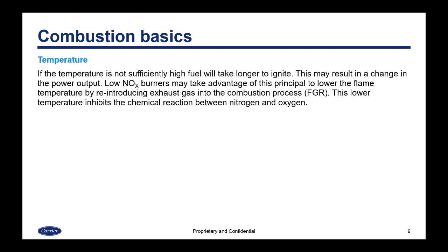If the temperature is not sufficiently high, fuel will take longer to ignite, and this may result in a change to the power output. Low NOx burners actually take advantage of this principle to lower the flame temperature by reintroducing exhaust gas into the combustion process. This is commonly known as FGR or flue gas recirculation. This lower temperature inhibits the chemical reaction between nitrogen and oxygen.